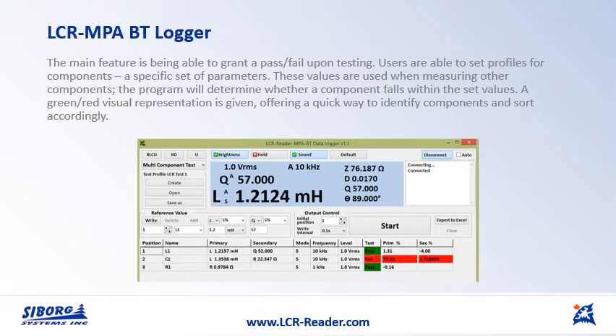You set a profile of a component, a specific set of parameters, like a component type, and then a secondary parameter, like for example, a serial resistance for the capacitance or inductance. And then when you do the measurement, the program actually can see if the measurement fits the specification of the component. You also specify the tolerance that's acceptable, and it shows you in green if it does fit into the tolerance range, or in red if it doesn't.